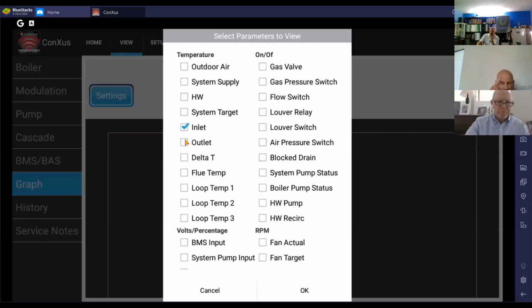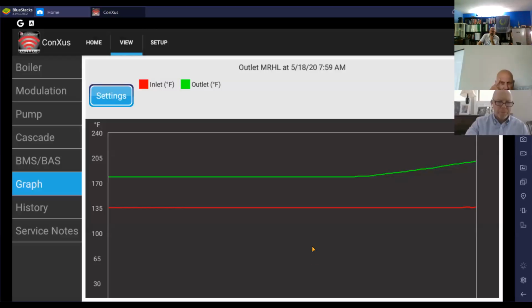Take a look at the inlet and outlet temperatures that were going on. I had a pretty steady inlet temperature, and then all of a sudden my outlet temperature spikes up. It's probably giving me an idea that we had a flow issue right here, or this is the moment where we fired and didn't have flow, and we spiked up through there. So take a look at that, and then talk to the guy on site, have him go start with taking a look at the pump and what was going on there.